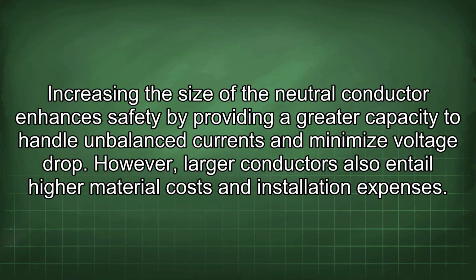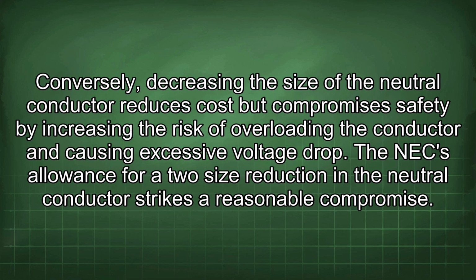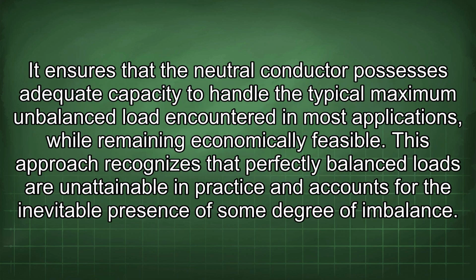Increasing the size of the neutral conductor enhances safety by providing a greater capacity to handle unbalanced currents and minimize voltage drop. However, larger conductors also entail higher material costs and installation expenses. Conversely, decreasing the size of the neutral conductor reduces cost but compromises safety by increasing the risk of overloading the conductor and causing excessive voltage drop. The NEC allowance for a 2-size reduction in the neutral conductor strikes a reasonable compromise. It ensures that the neutral conductor possesses adequate capacity to handle the typical maximum unbalanced load encountered in most applications while remaining economically feasible. This approach recognizes that perfectly balanced loads are unattainable in practice and accounts for the inevitable presence of some degree of imbalance.